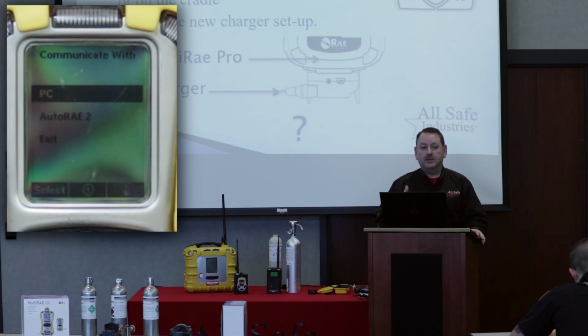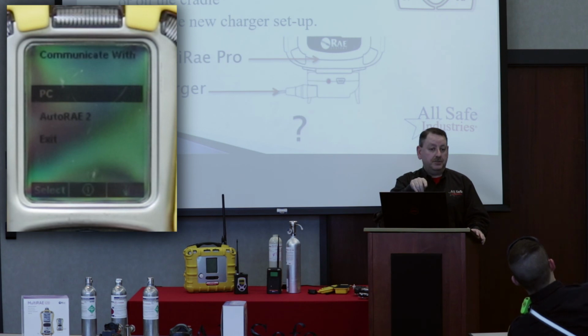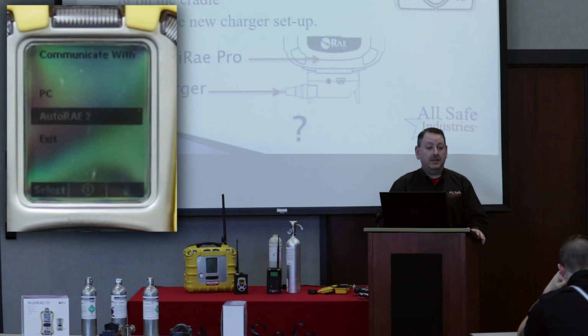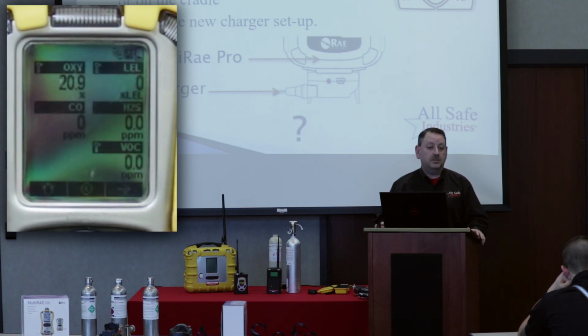So remember earlier how I said when you're first using the AutoRae 2, you'll start with the meter off. You'll put it in the cradle. It'll go through a warm-up sequence and then give you the choice for a bump or a cal. If you already have the meter turned on, you can go to this screen, enter communication mode, select, drop down to AutoRae 2, select again, and then it will be ready to talk to an AutoRae 2 cradle. So then you could literally take the instrument, put it in a cradle, and it will be immediately ready to run a bump check or a calibration. And then if you hit the arrow button one more time, you'll come back to the home screen, which is the main page where you're getting your real-time gas readings.